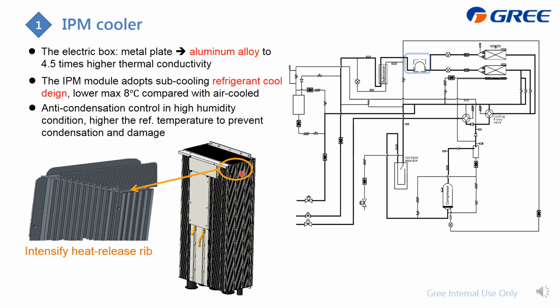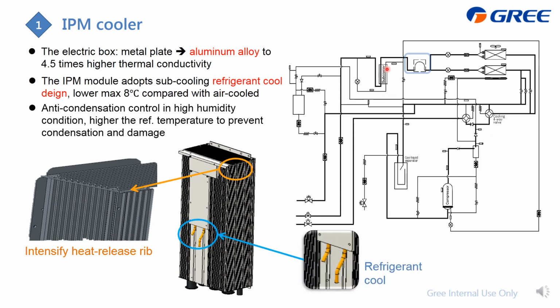And for the IPM cooler, you may worry that on the surface of it, in high humidity conditions, we will get condensing water. And the condensed water, if it is generated at the IPM, will also very easily cause damage. For this one, we already considered it, and we also have the solution, which is to raise the temperature of this refrigerant to avoid the refrigerant being lower than the dew point, so this will not generate condensing water.